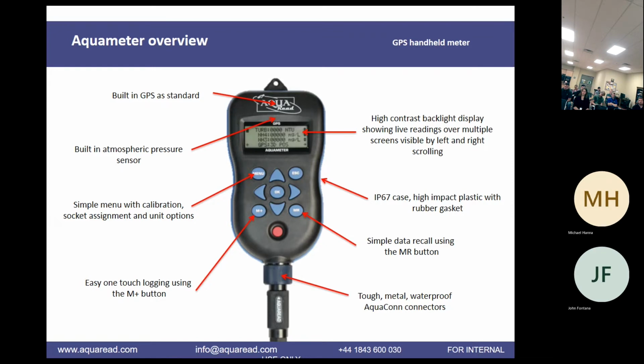You can store your GLP data as well. The calibration data, or how successful your calibration was, can be stored and then recalled, and you can export that information. So if customers ask how good your calibration was based on what the manufacturer says it should be, you can extract that calibration data from the meter and include it in your field reports if needed.